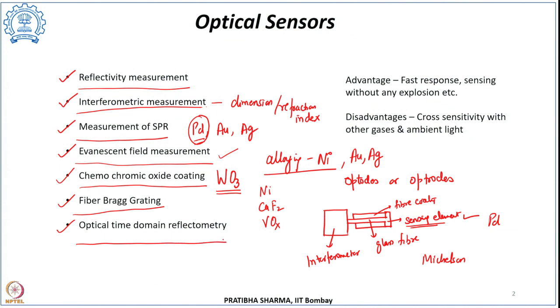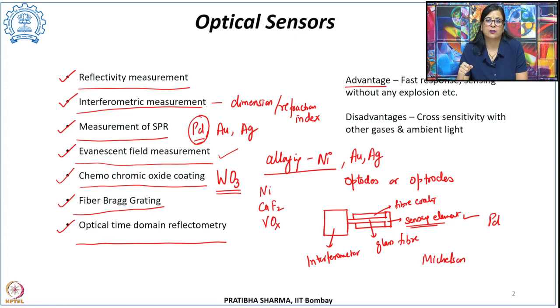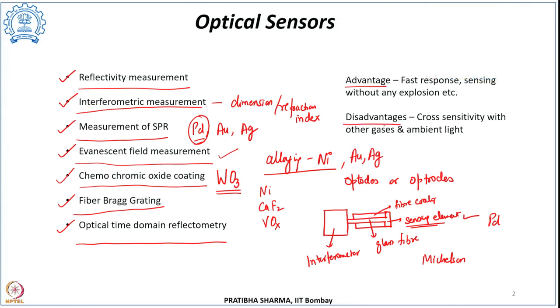Another technique is optical time domain reflectometry, where reflectance is measured along the entire length of the fiber optic cable rather than at a single point. This enables distributed hydrogen sensing using only one device, with spatially resolved signals over a longer distance. Optical sensors have advantages including faster response and reduced risk of explosion since no oxidizers or electric current are required. However, they have a disadvantage of cross sensitivity, where signals from other gases or ambient light interfere with hydrogen detection.